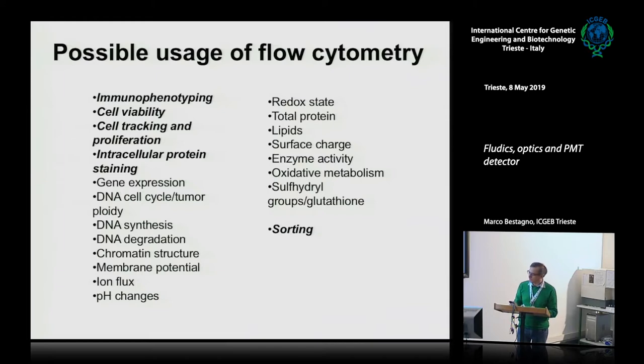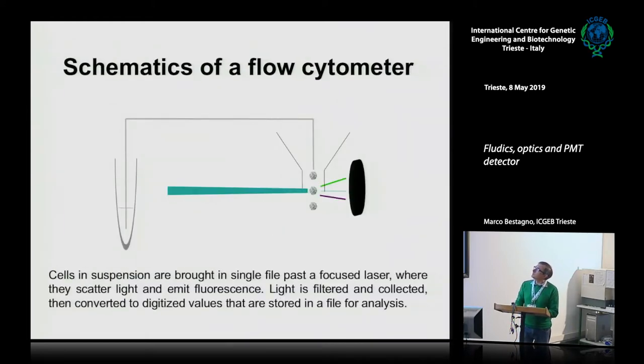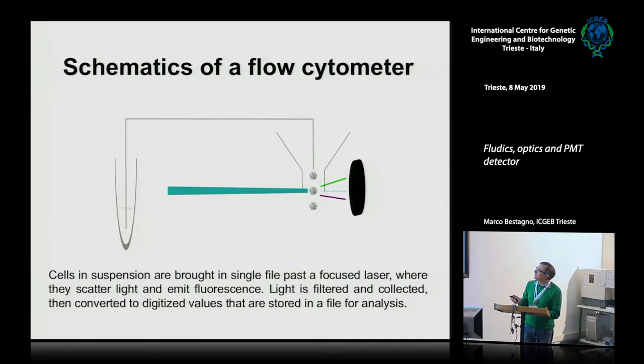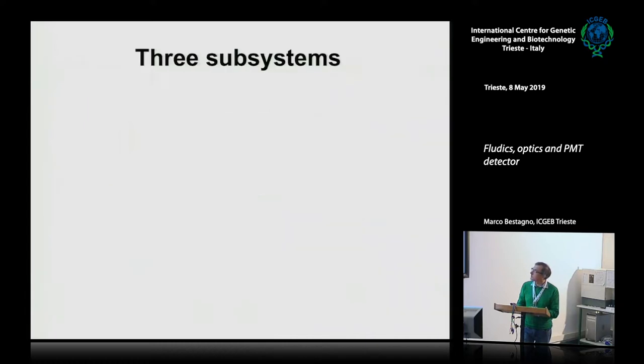The basic schematic of a flow cytometer is as follows: a tube containing the samples in suspension is brought by the fluidic system to the interrogation point, where cells intercept a laser beam. They scatter light or produce fluorescence that is detected by a detector and converted to digitized values that are stored and can be analyzed. A flow cytometer is therefore divided into three subsystems: fluidics, optics, and electronics.